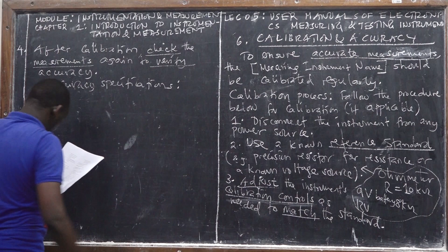The manufacturer will declare the accuracy specification for the different instruments. For instance, stop writing. In the user manual, you see the accuracy specification called voltage measurement. So the voltage measurement accuracy specification will be plus or minus X percentage. What does it mean? This is percentage error. Do you remember percentage error? It means this is tolerable error, in other words tolerance.